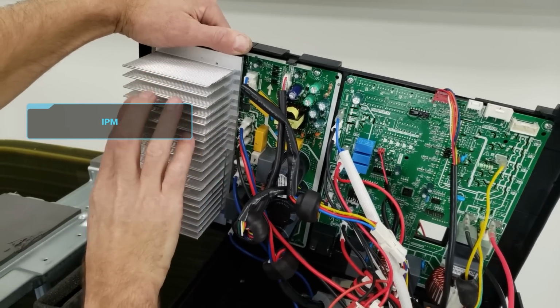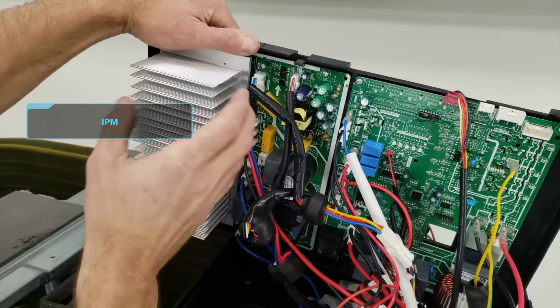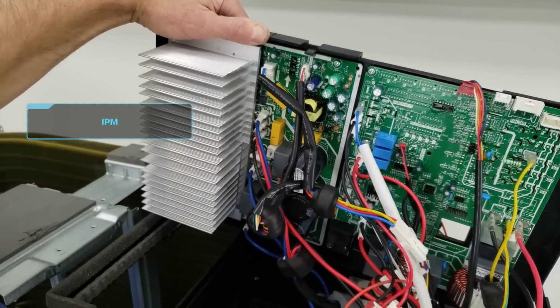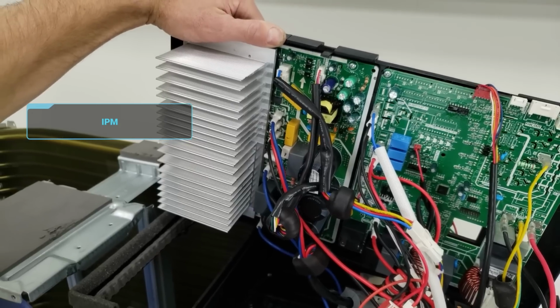And in fact, the intelligent power module usually has an aluminum heatsink that is in the airstream of the outdoor unit. So that outdoor fan is pulling air not only across the coil, but across the IPM, not the whole module, but just the heatsink. And the IPM is doing that conversion, changing basically single phase electricity into 3 simulated phases of AC power to power the compressor.